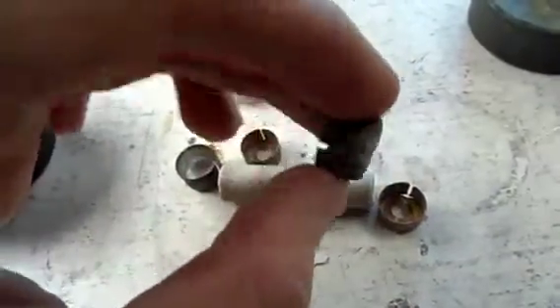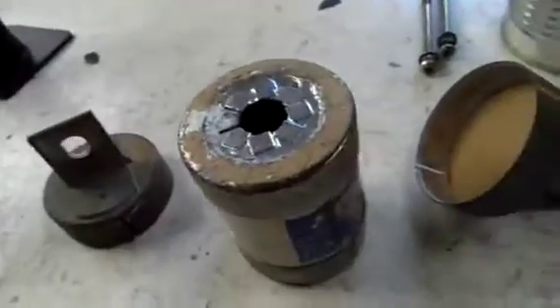These smaller ones are only about 10mm in diameter, but they get much bigger than that. Last but not least we've got this bigger one — I'm guessing it's a power line fuse or something — 315 amps at 660 volts AC. It's got a bit of rust on it; I do have another in better condition so I'm keeping that one. Down in there you can see the individual straps soldered to the inner end caps, and you've got your gasket which contains sand and moisture, then the outer cap which is press-fitted.